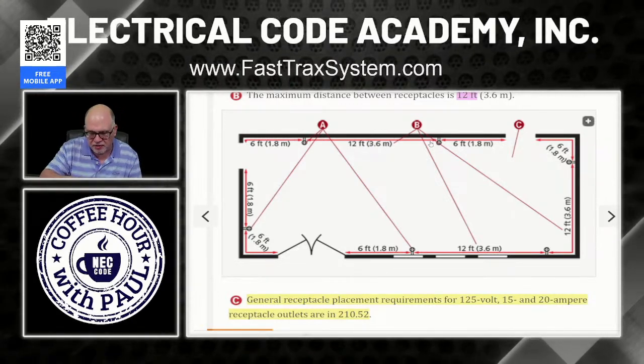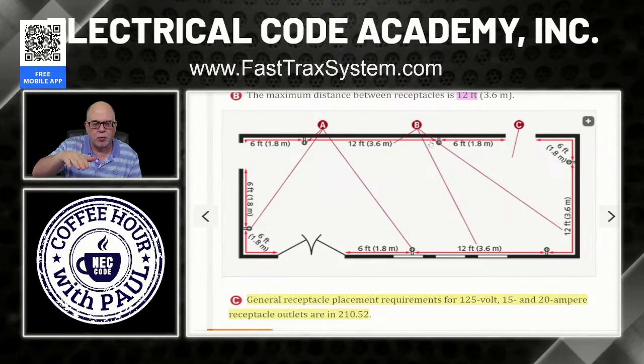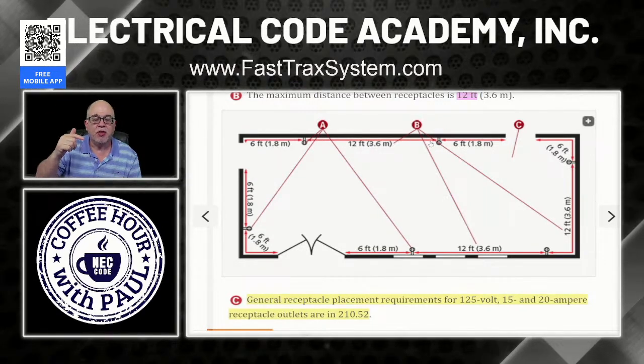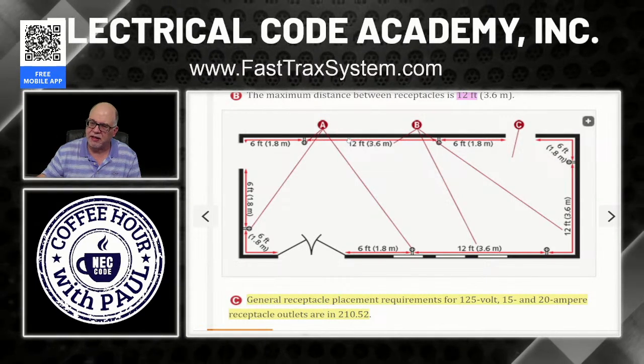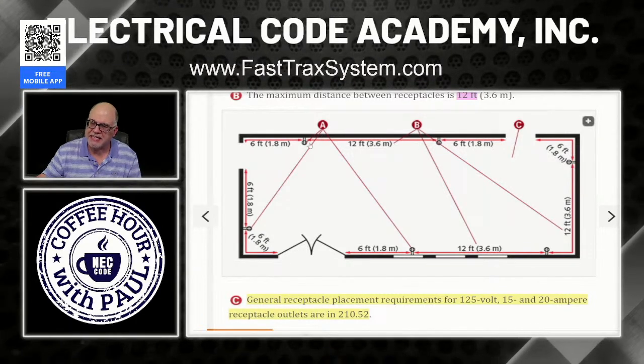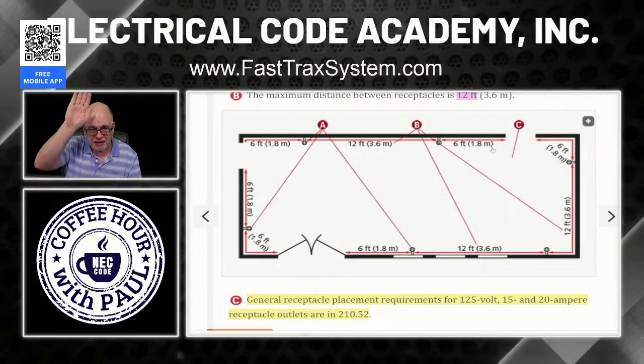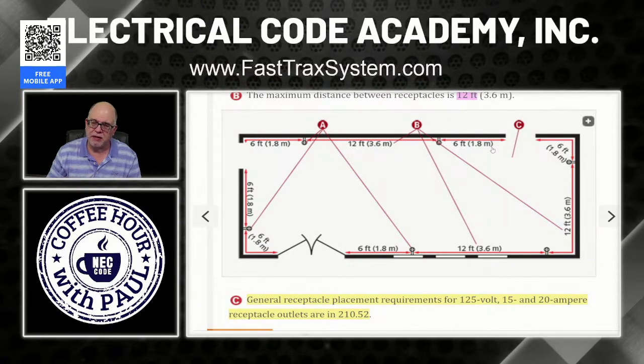Nothing says it has to be 16 inches off the floor, 18 inches off the floor. It could be 2 feet off the floor. Nothing says that it can be, but the moment that it goes higher than 5.5 feet, then I would have no receptacle in this wall space, and essentially I'd have nothing for this whole span. For 18 feet, I would have nothing as far as the code's determined, because I put that receptacle up higher than 5.5 feet. So I would have to add a receptacle down low.